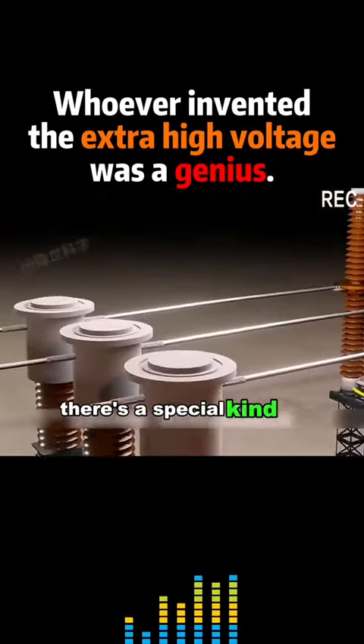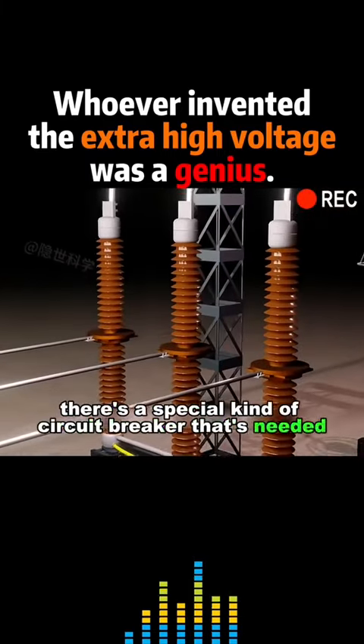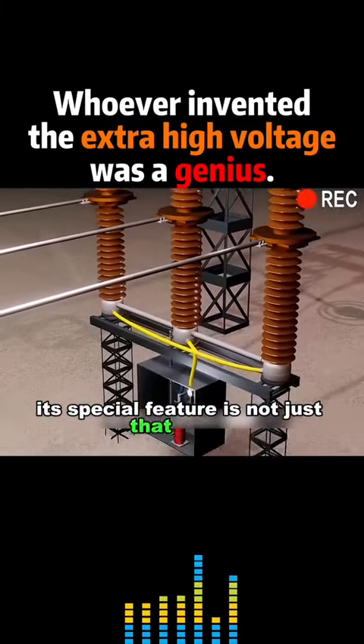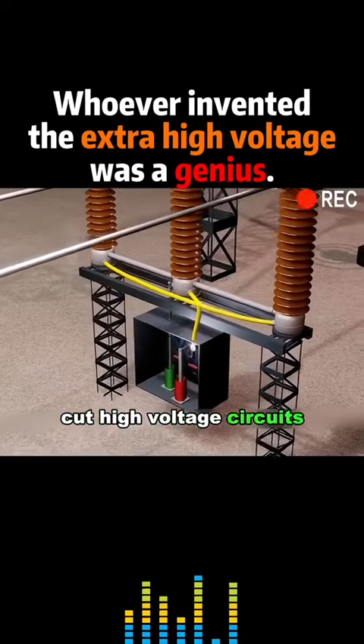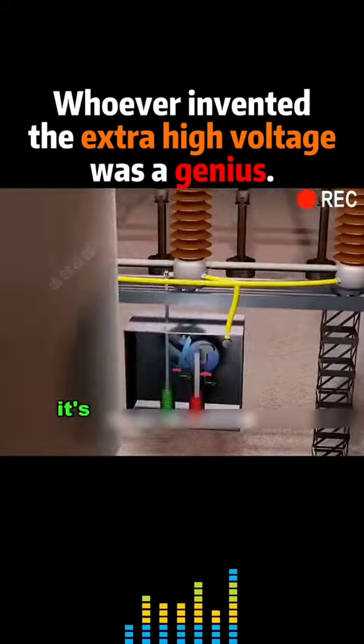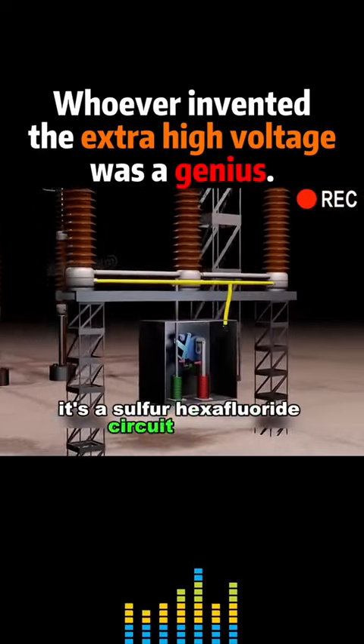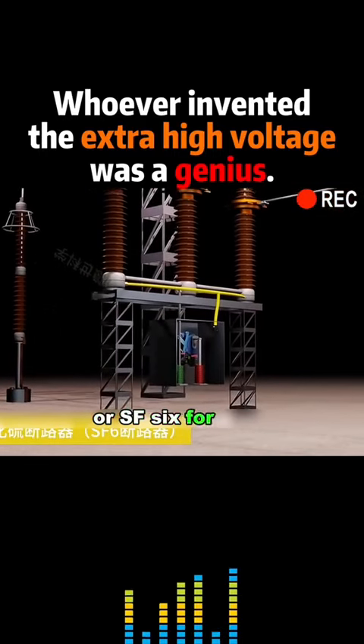Well, there's a special kind of circuit breaker that's needed. Its special feature is not just that it can cut high voltage circuits, but the way it works. It's a sulfur hexafluoride circuit breaker, or SF6 for short.